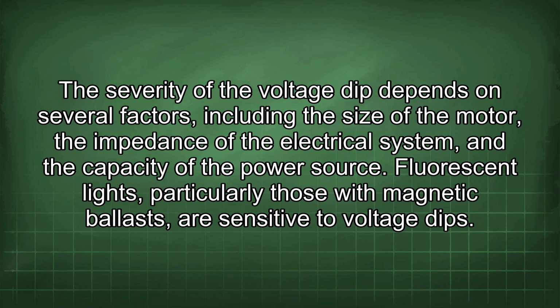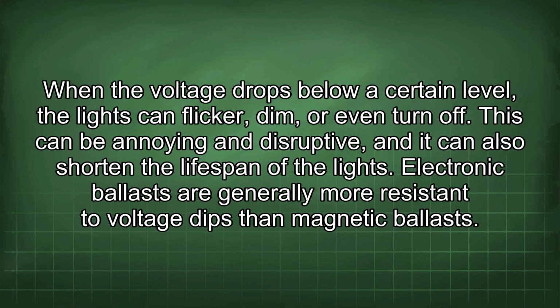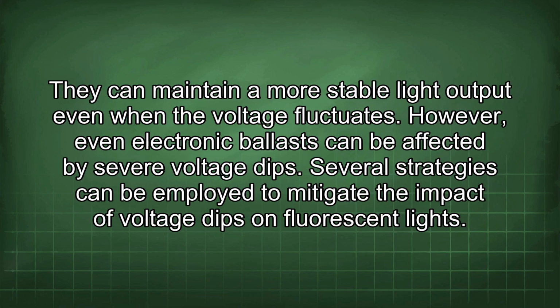Fluorescent lights, particularly those with magnetic ballasts, are sensitive to voltage dips. When the voltage drops below a certain level, the lights can flicker, dim, or even turn off. This can be annoying and disruptive, and it can also shorten the lifespan of the lights. Electronic ballasts are generally more resistant to voltage dips than magnetic ballasts. They can maintain a more stable light output even when the voltage fluctuates. However, even electronic ballasts can be affected by severe voltage dips.